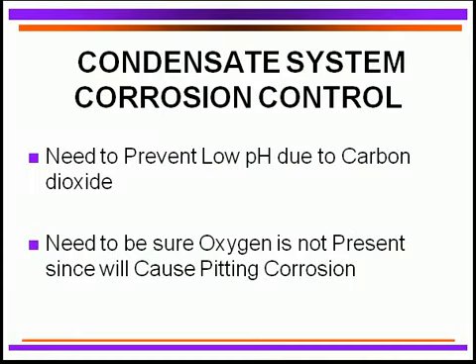The last area of the complete boiler water circuit is the condensate system. We need to maintain good corrosion control of the condensate lines — that's with steam being condensed in your operations, whether it's for heating or producing electricity with turbines. We need to prevent low pH due to the presence of carbon dioxide, neutralizing that acidity. We also have to consider whether oxygen is present in the steam or condensate system, because if it is, it's going to cause pitting attacks.